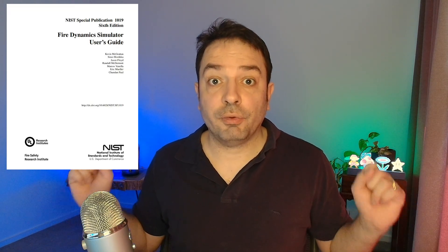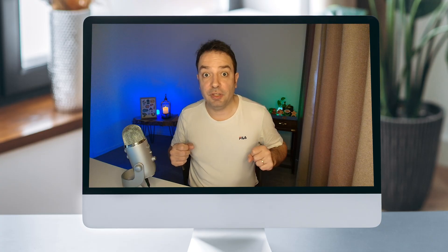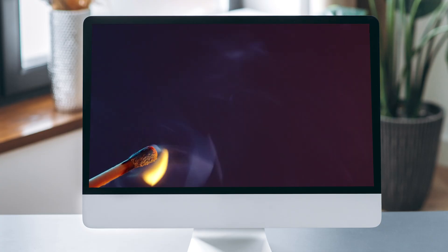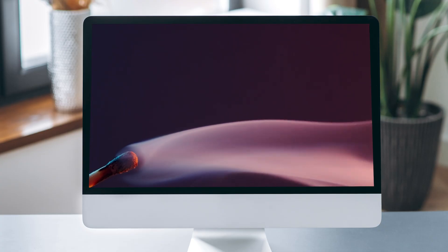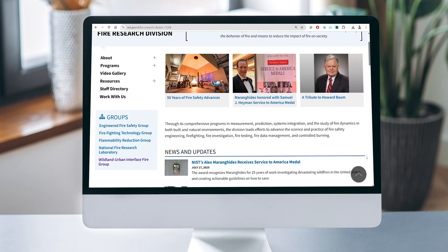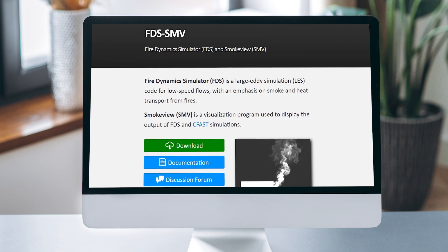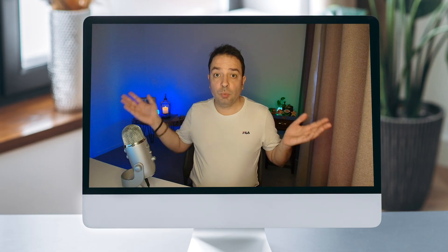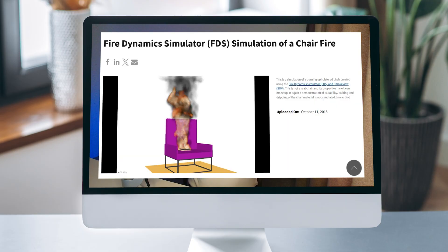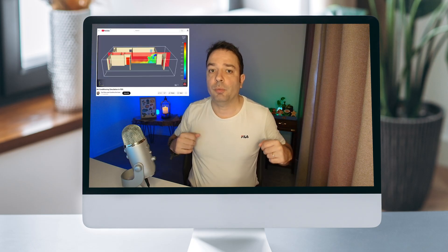The tool we are going to analyze today is BlenderFDS, and it works with FDS. FDS stands for Fire Dynamics Simulator — it's a really powerful CFD software developed to simulate the spread of smoke and fire inside a building geometry. It was developed by the Fire Division at the National Institute of Standards and Technology in the USA. FDS is a large eddy simulation code for low-speed flow, designed focusing on heat transfer and fires. It can be used for many other applications, but always be careful about the main assumptions behind this software.